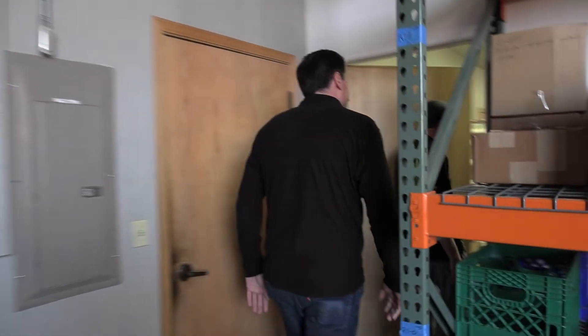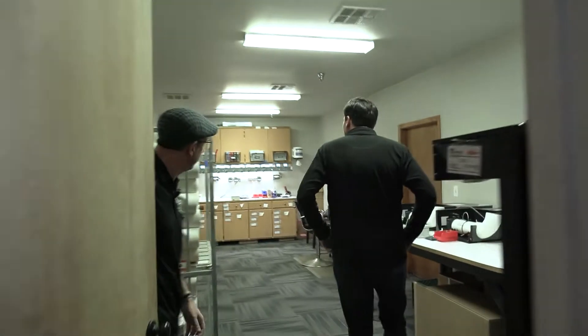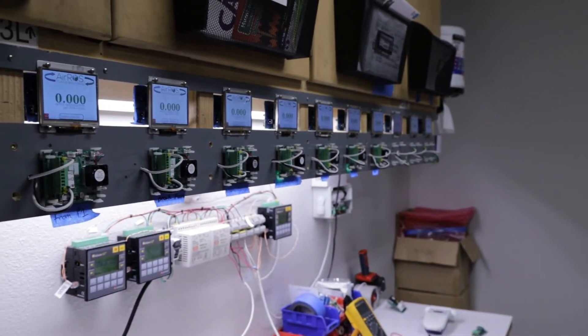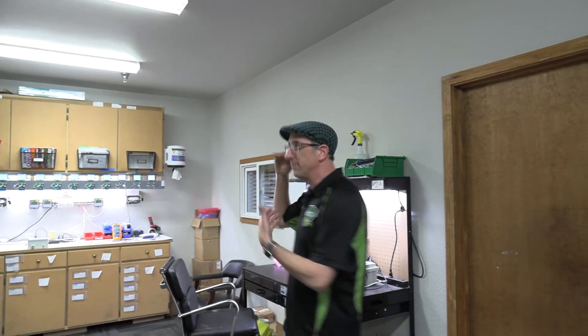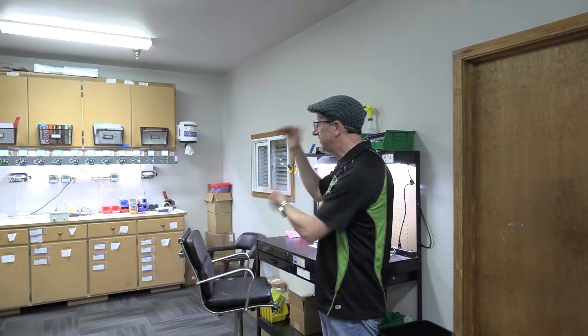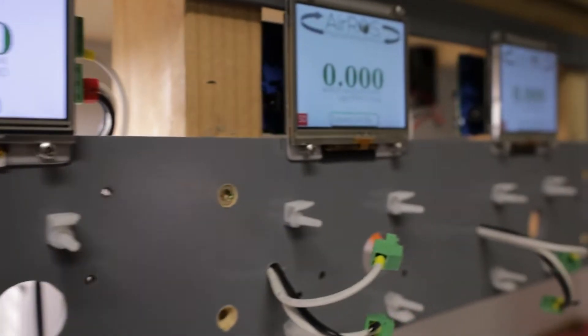This little room has its own autonomous HVAC system and we can run little tests in here — most of the time it's for testing sensors. We test sensor heads that come in to make sure they're within our calibration spec. They come in calibrated with certificates, but we want to verify that because things happen in shipping. We test them here before they go on the shelf, then put them in the unit and retest with a full system before it goes to the customer. Because we're measuring parts per billion — if it drifts five and I'm trying to keep 30, that's out of calibration. We suggest calibration every six months, and we have customers that religiously have us come every six months for preventative maintenance.